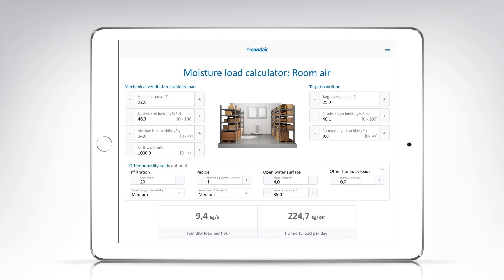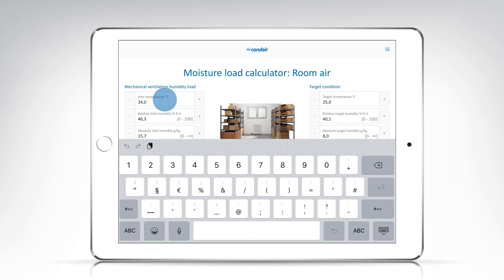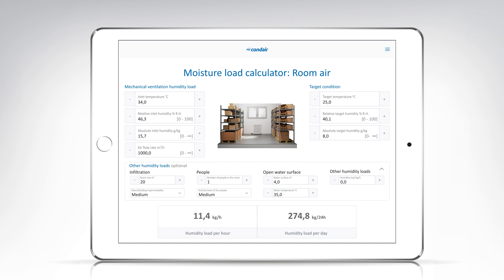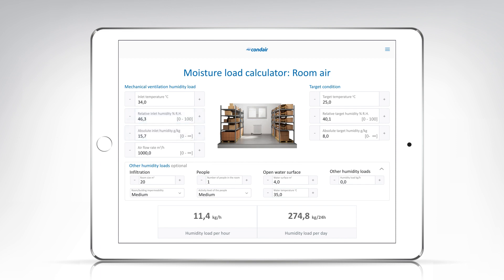For the calculation of swimming pools, however, we recommend using the moisture load calculator swimming pool, because this calculation profile is more specific to the situation of a swimming pool. To enter the parameters, you can either use the shortcut keys or click directly in the input field to enter the values using the keyboard. For air humidity, please note that relative and absolute humidity are correlating values which for physical reasons cannot be changed individually. An adjustment of relative humidity will therefore always change the value of absolute humidity, and vice versa.